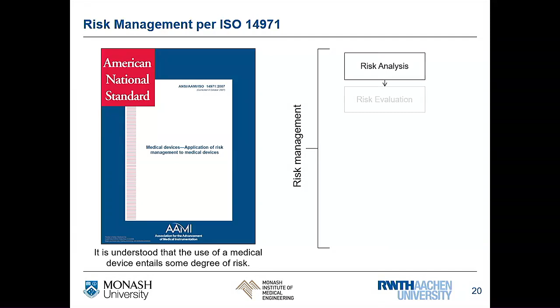Also, this is standardized according to 14971. It's a very famous standard from ISO, the International Standardization Organization. And you always have to know, and that's what some people forget when sometimes the press comes and says something happened with a device, there is never 100% safety. We all know that. Even an airplane, as we see, can fall from the sky, so we should always be aware there is never 100% safety on these devices. So what you do is basically you assess your risk. That means you look at what kinds of risk you have, and then you try to implement risk control and mitigation processes. That means to either test it or see how you can improve it.